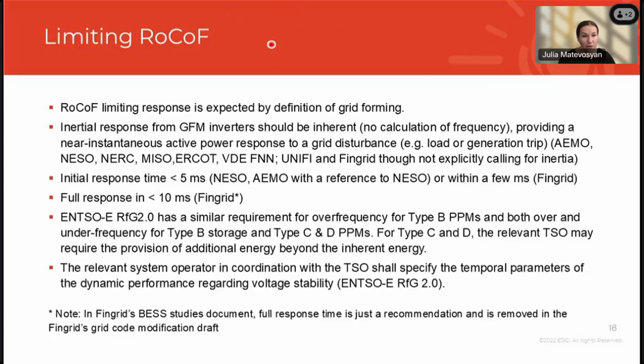Then limiting RoCoF. It's again, this response is expected by definition of grid forming. So most of the operators define it as inertial response from grid forming inverters, which should be inherent and not calculate frequency and not be like controlled type of response. And it needs to provide nearly instantaneous injection in active power in response to grid disturbance, such as load or generation trip. UNIFI and FinGrid requirements do not explicitly call it inertia, whereas others do.